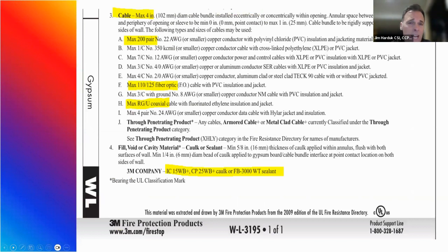And again, as I had mentioned before, it's not uncommon to have one system drawing that addresses multiple fire stop conditions. For this example, there's several different types of cables that can be used in this assembly. And at the bottom of the page, again, it'll identify what 3M products can be used to address that fire stop condition. So in a large percentage of our tested systems, there's going to be more than one product that is applicable for use in that application. In this particular example, it lists 3 different types of 3M sealants. It has our IC15WB+, the CP25WB+, and the 3000 series, which is a silicone-based sealant.